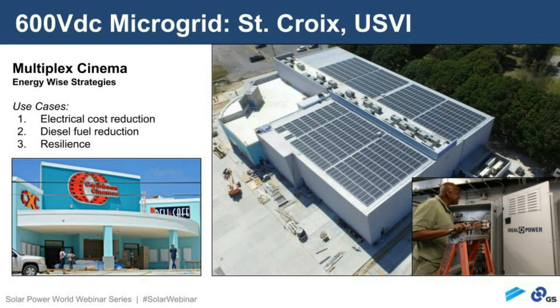The overall architecture for this ended up being 3 big Caterpillar diesel generators, and multi-port DC-coupled inverters, so that the PV and the battery were both brought into string inverters with multiple ports. So you have a 600-volt battery bus, a 600-volt PV bus, and everything is processed and then controlled by a site controller.